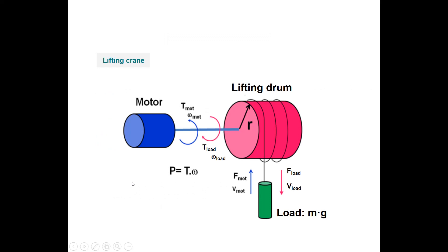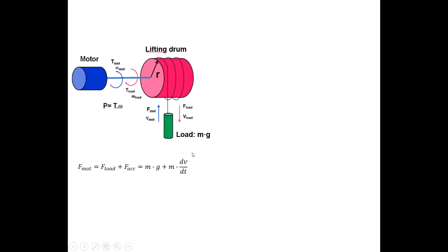In this example, we have a motor which drives a lifting drum, and connected to that lifting drum we have a load. The force acting on that load is m times g, where g is the gravitational acceleration. We have a load force and a load speed, and that load force becomes a load torque, while the load speed is transformed to an angular velocity. When we want to move that load, the motor force equals the load force plus the acceleration force: F motor equals m times g plus m times a, where a is the derivative of the speed, dv/dt.